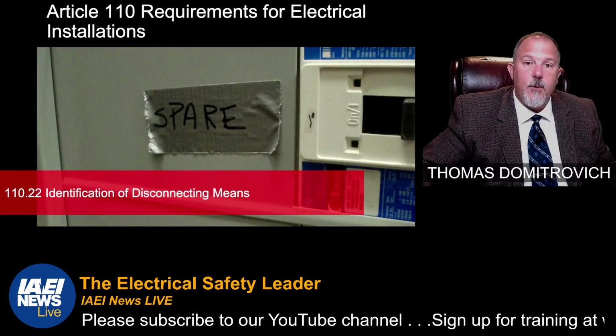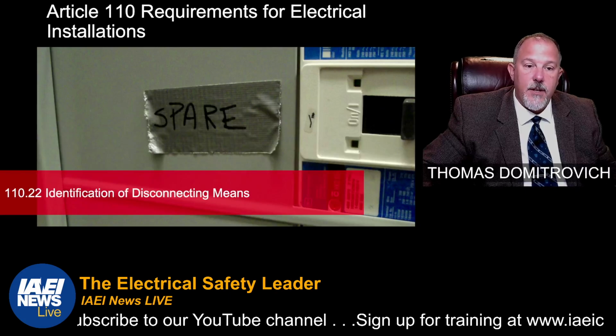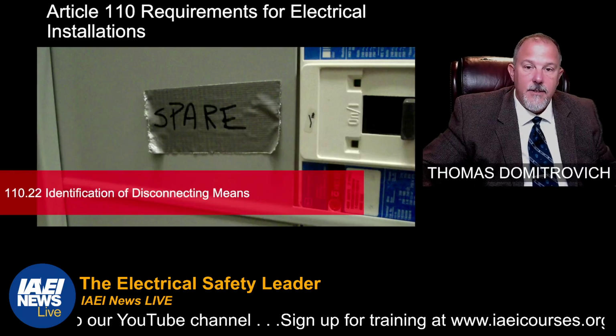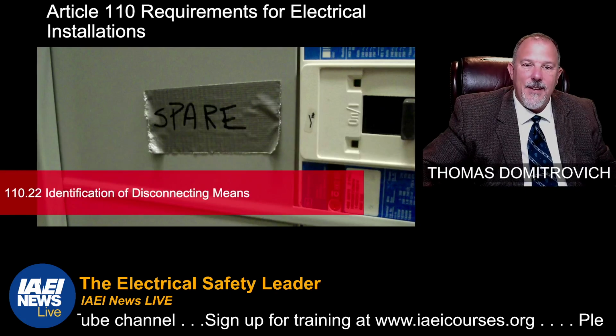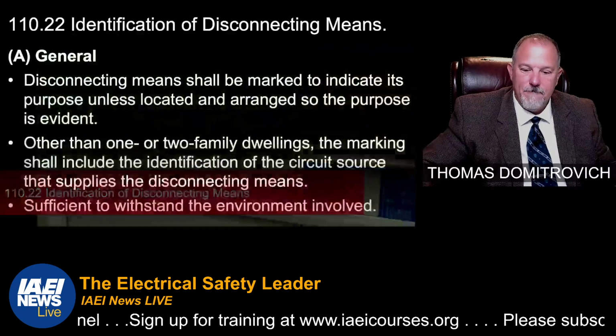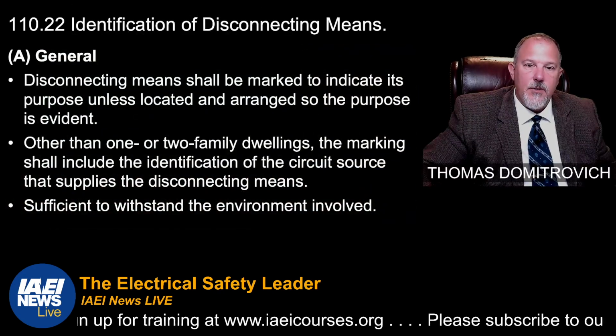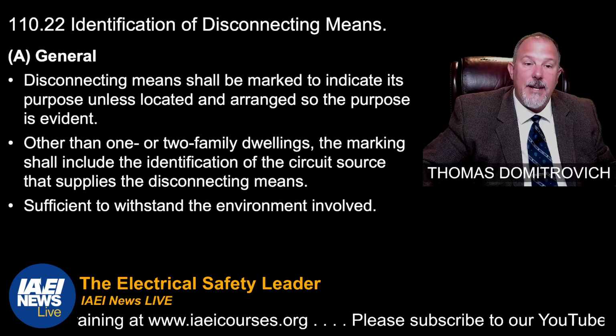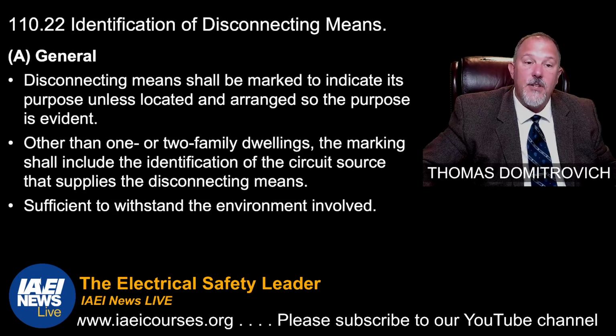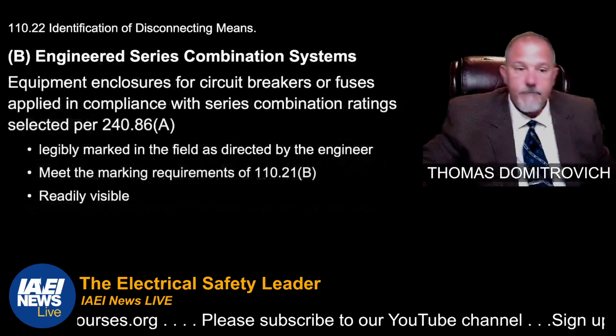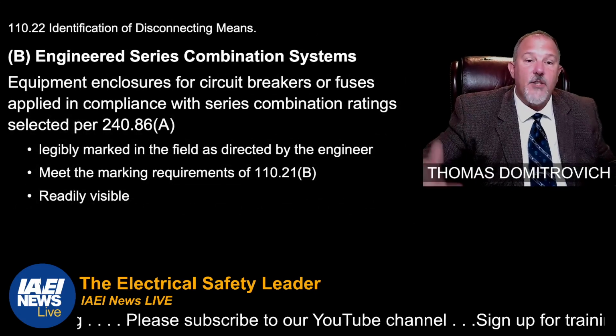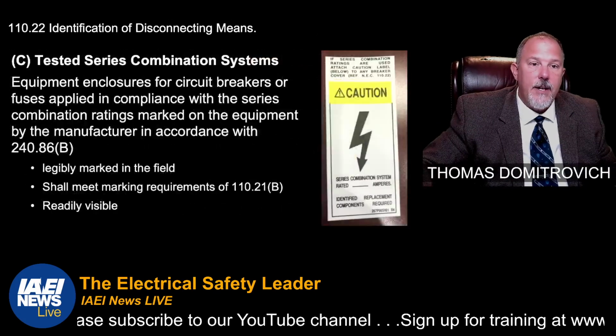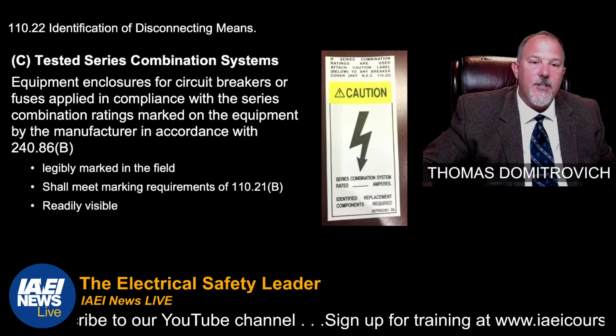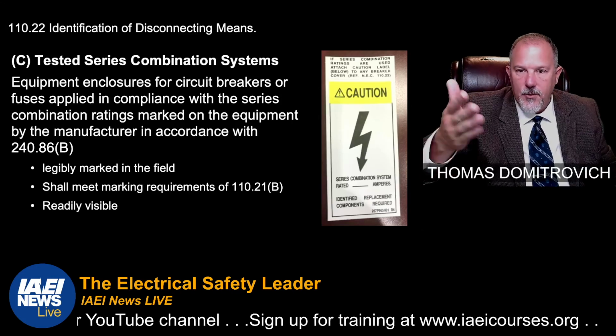Article 110, requirements for electrical installations. This is the identification. I love the duct tape rules, right? 110.22, the disconnecting means shall be marked to indicate its purpose unless located and arranged so the purpose is evident. Engineered series ratings. We already talked about series ratings. That's in 110.22. You'll see labels like this.